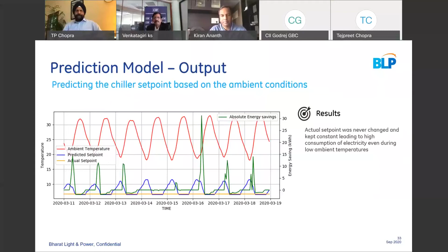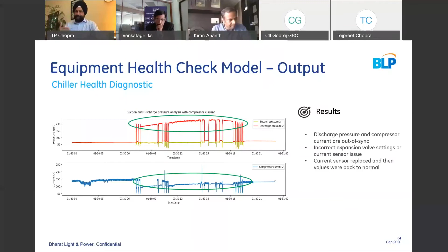What you can see out there in the chart on top is the suction and discharge pressure analysis, compared with the compressor current. So what we found in this situation was that the discharge pressure and the compressor current were both out of sync. And that was causing a huge amount of variance in the energy consumption in this building. In this particular case, what we had to do was change the sensors and fix this out of sync situation to drive the energy efficiency with the algorithms.